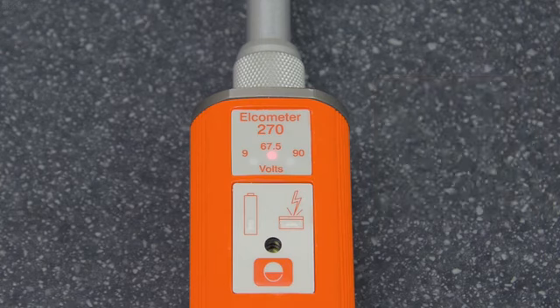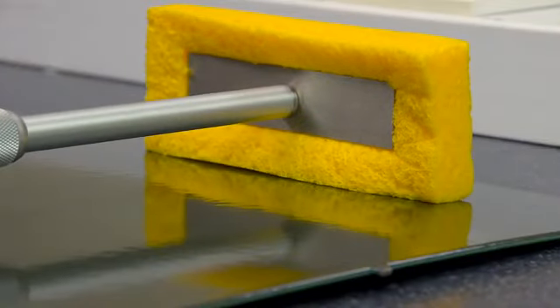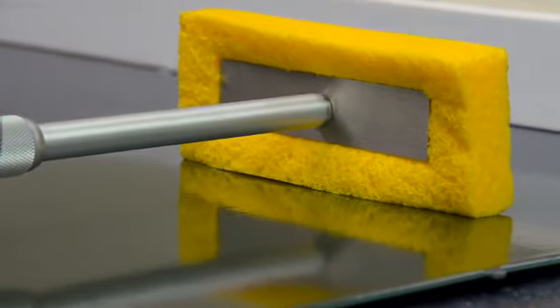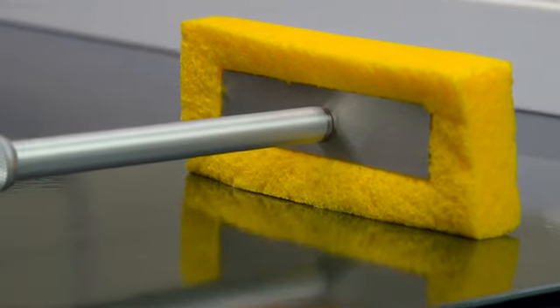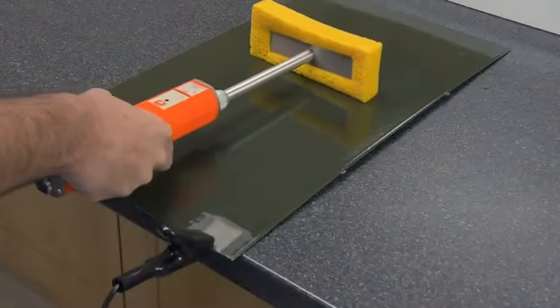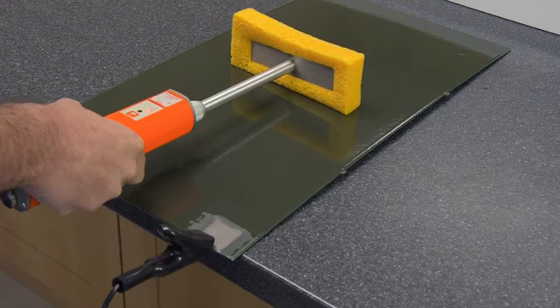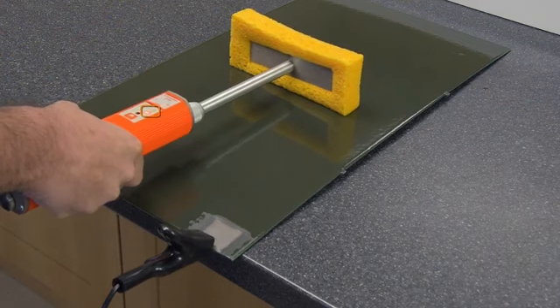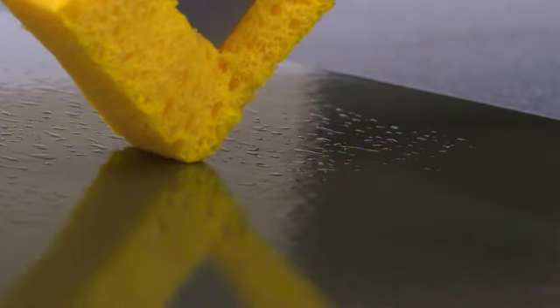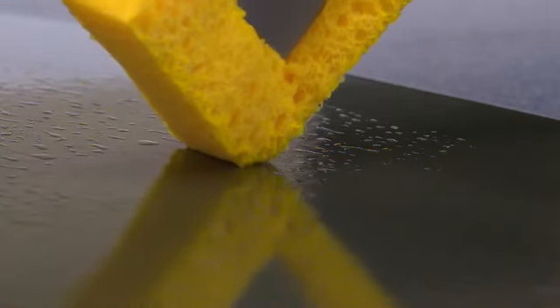Every time the tester is switched on or the voltage is changed, the Elcometer 270 automatically tests the calibration of the internal voltage and sensitivity. With the calibration tested, you can now pass the sponge over the coated surface to test for pinholes. If the sponge passes over a pinhole, the Elcometer 270 will instantly alarm. If you need to locate a pinhole more precisely, simply retest the area using just the corner of the sponge.